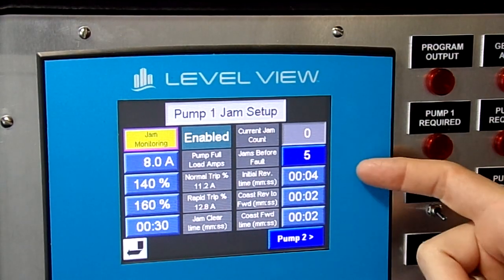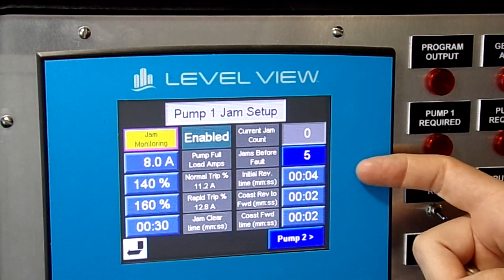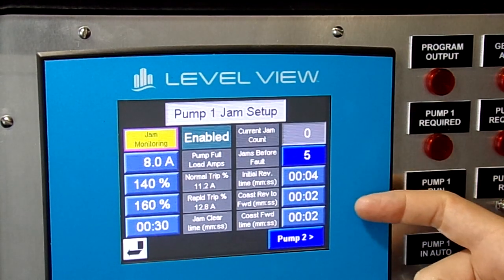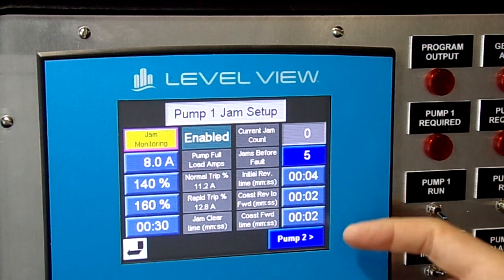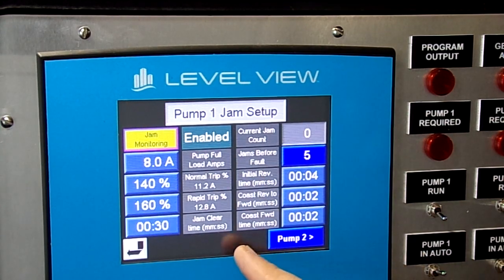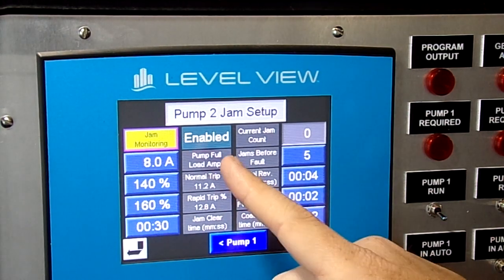We also have timers for when the station is running forward and how it's going to coast to a stop in between its reversing functions. This will need to be set up for both pumps 1 and pump 2.